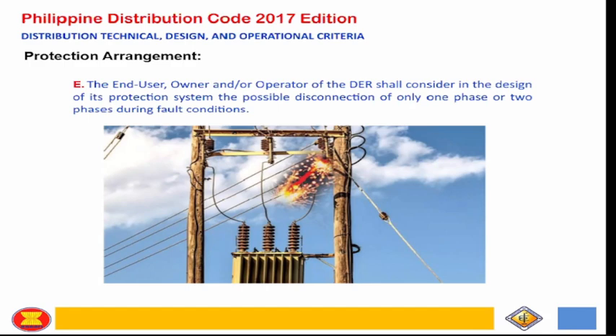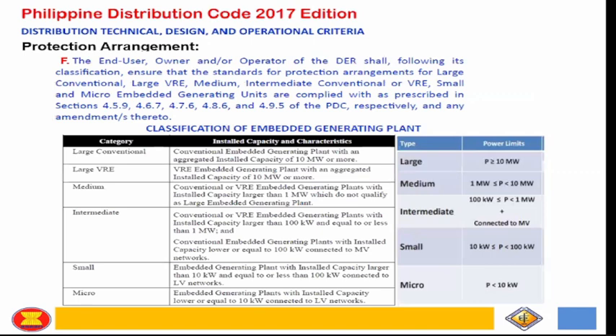If there are lateral fuses with a line to ground fault, there is a real possibility of single phasing. Then you must have appropriate protection for that scenario. So this is stated in the distribution code.